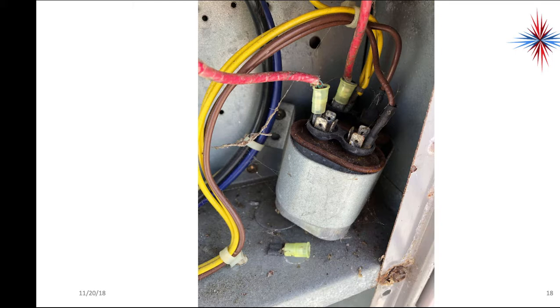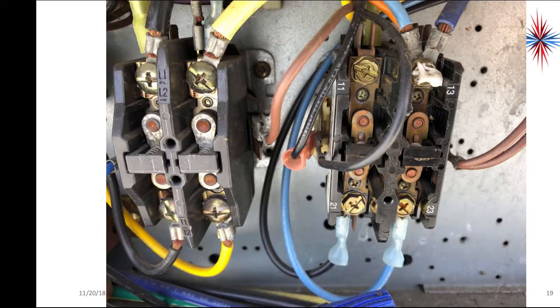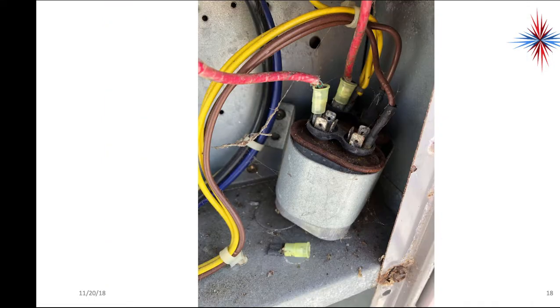Take a look at the capacitors. I do all my electrical checks first. Okay, you'll notice that the contactors, if this was a preventative maintenance, I would be recommending both of these contactors be replaced. There's starting to be burning marks here. Again, nothing that signifies voltage surge, and the fact that there's still some factory default anti-tamper here tells me that this contactor hasn't been replaced yet. Don't see any burnt wire, see a lot of rust.